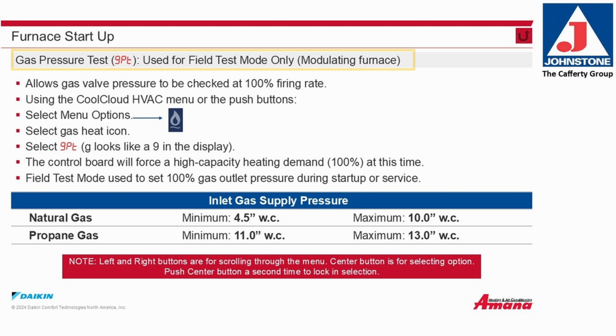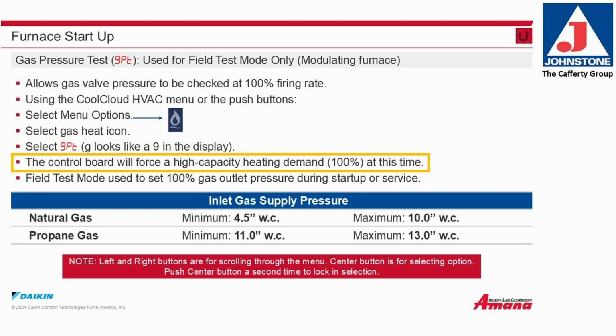Furnace startup. Gas pressure test, used for field test mode only on the modulating furnace. Allows the gas pressure valve to be checked at 100% firing rate. Using the CoolCloud HVAC menu or the push buttons, select menu options. Select the gas heat icon. Select GPT. The G looks like a 9 in the display. The control board will force a high-capacity heating demand, 100% at this time.